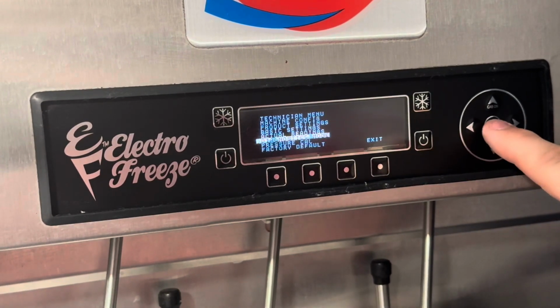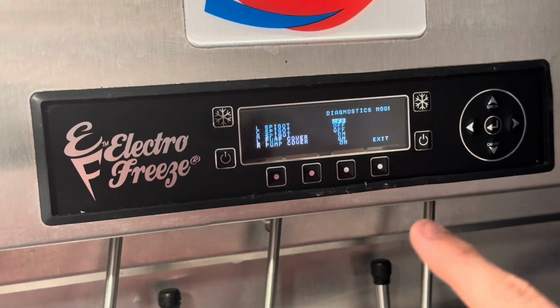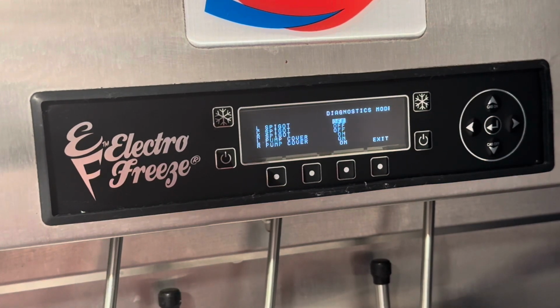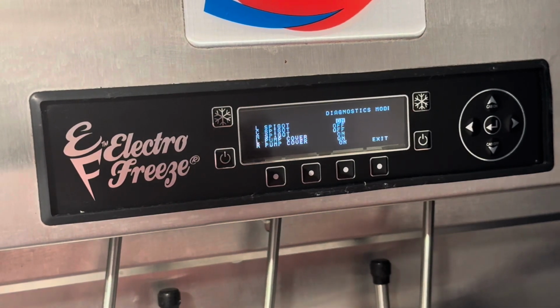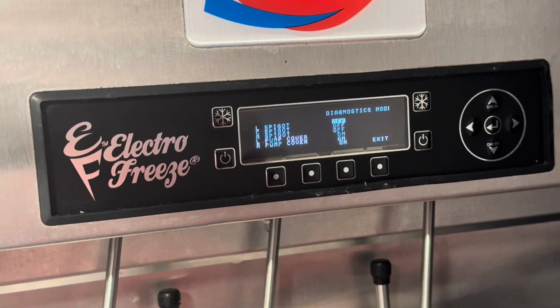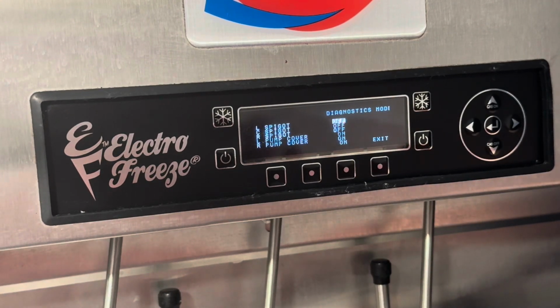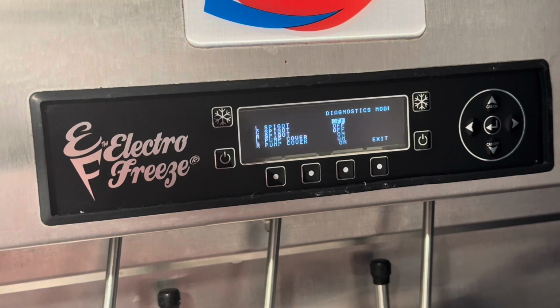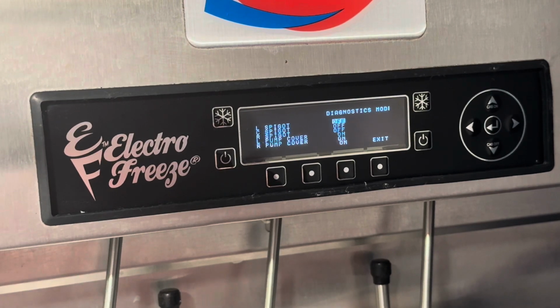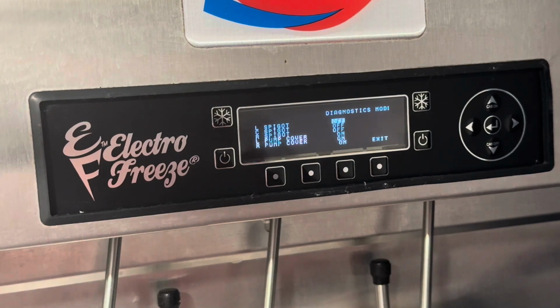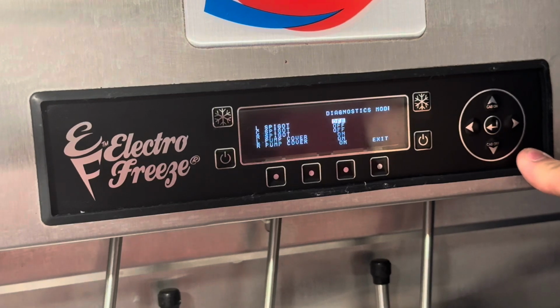Diagnostics mode, this is really useful right here. We're going to enter this. Now left spigot, center spigot, and right spigot. So if we open the spigot, you hear the click, it'll show on. We'll pull the center. Now one thing you want to make sure is that these spigots turn all the way off when you shut the machine, and it reads off. If they get stuck on, you're going to have a spigot error displayed on the front of the screen. So this is something very useful to note, to make sure these are all off when they're all closed and all on when they're all open.